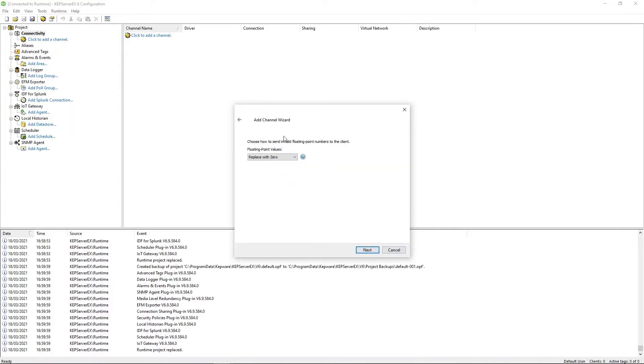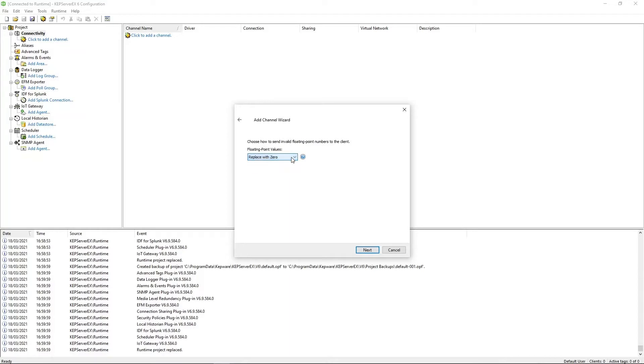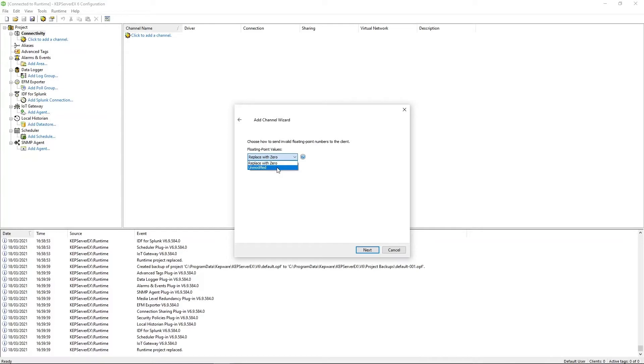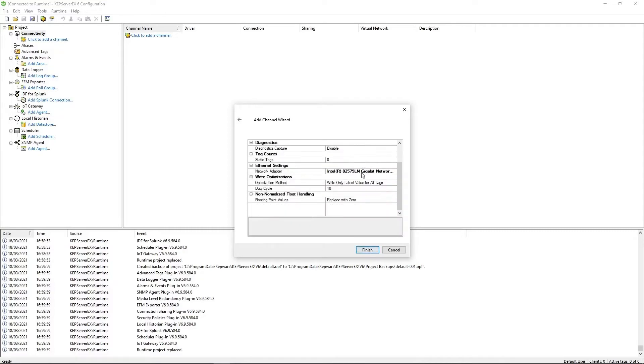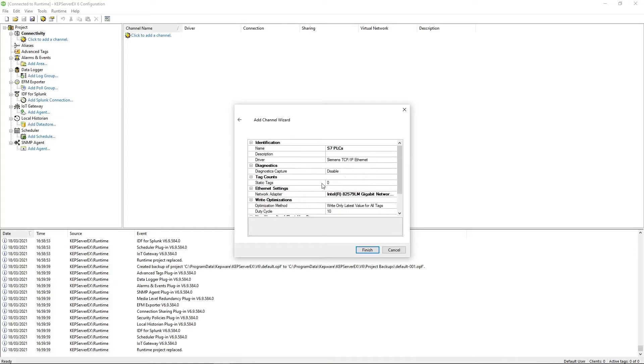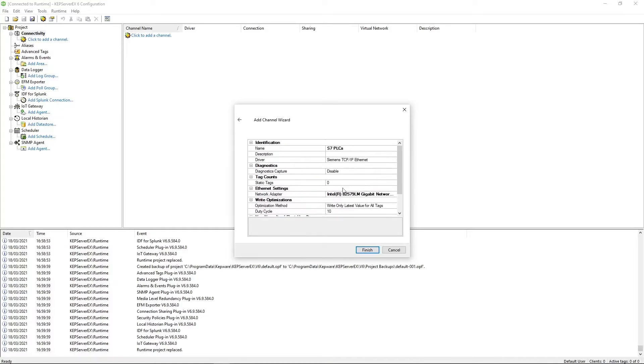And this lets you choose how to deal with invalid readings coming from the PLC. So these would be numbers like NAN or not a number, positive infinity, negative infinity, numbers that don't actually make sense, but you need a way of dealing with them. Some devices, if you don't replace it with zero, you're going to run into issues. So this is the default, but in other cases, you may wish to deal with it by yourself, in which case unmodified may be an option. Next. And finally, this is just a summary of the add channel wizard, which goes through all the options you've selected and you can make any changes. Once you're satisfied, just click finish.